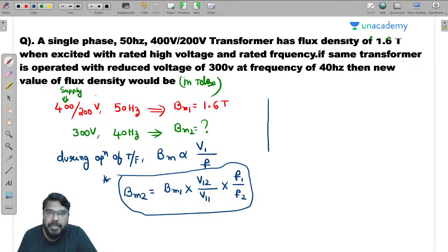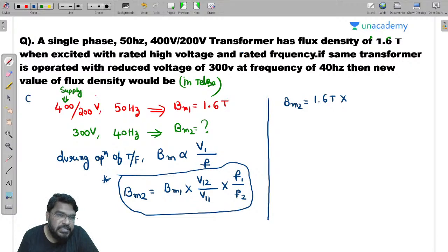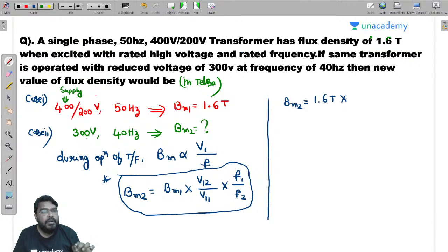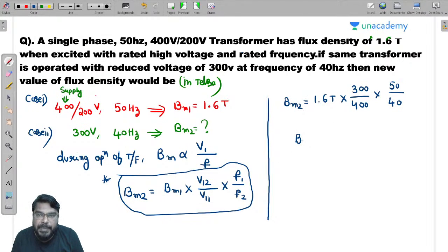Now substitute: Bmax2 equals Bmax1, which is 1.6 Tesla, multiplied by the applied voltage in case 2, which is 300 volts, divided by the applied voltage in case 1, which is the rated high voltage of 400 volts, multiplied by the frequency ratio: case 1 frequency is 50 Hz and case 2 frequency is 40 Hz. Now simplify this to get Bmax2.